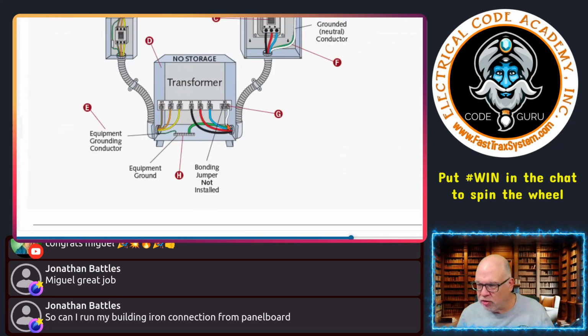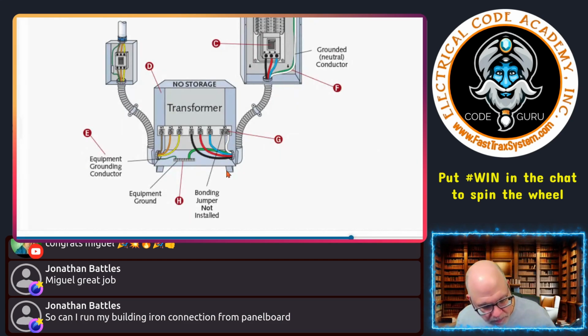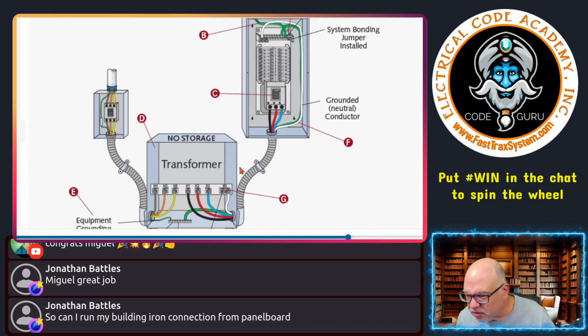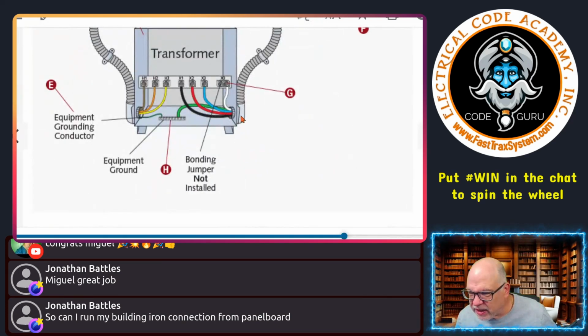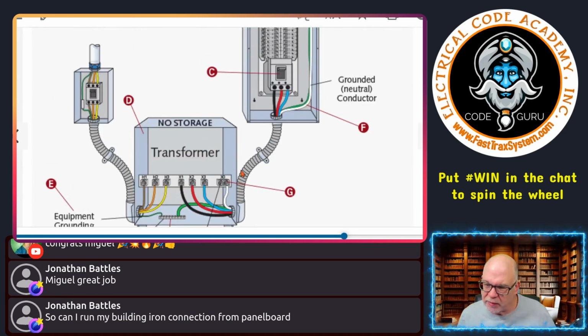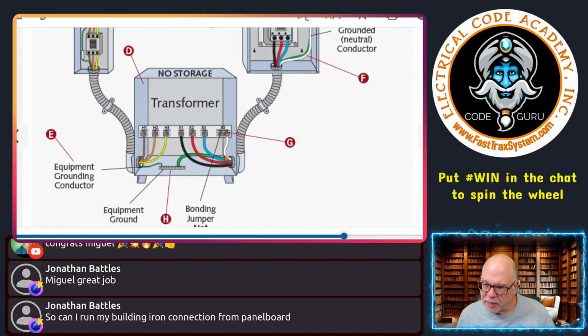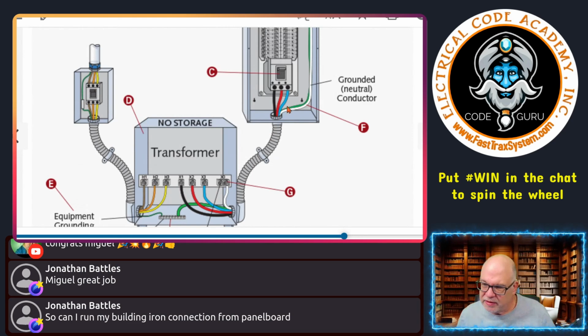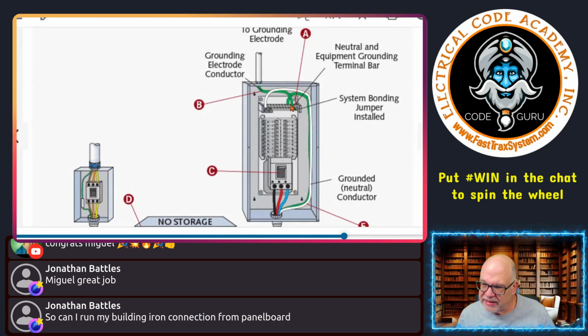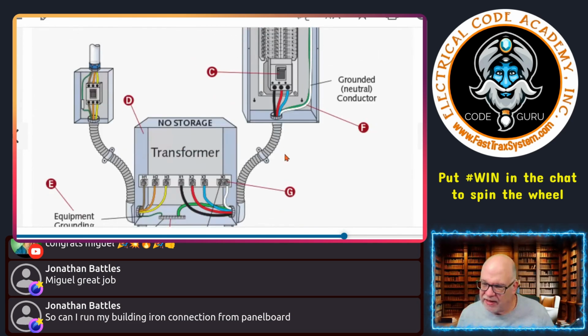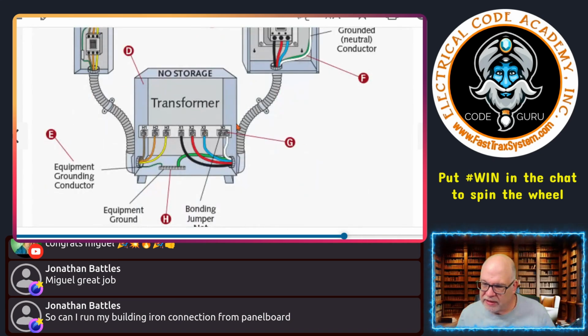And then you'll also notice over here, I guess I can zoom in a little bit. You'll notice over here that this is a punched KO, and you don't see any lay-in. What you see is, because this is flexible, it is bonded at each end. But you had to run a supply side bonding jumper up, over, and make the connection here. See that? So that maintains the integrity between here and here.